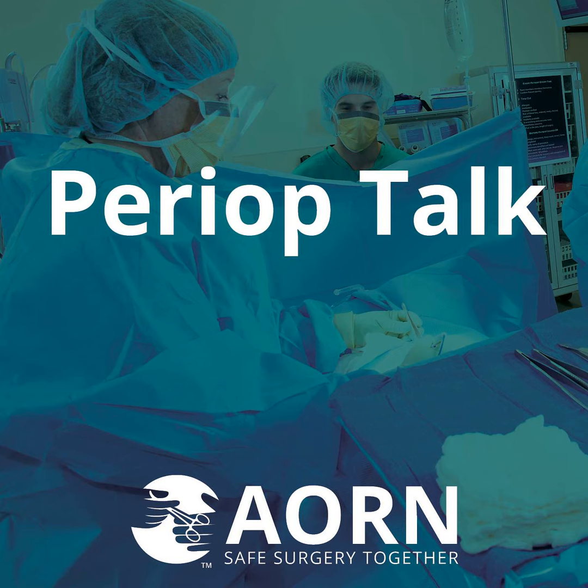Review the IFU of those pouches and the items that you're putting into pouches, and coach your team. Give just-in-time coaching, looking at the seal quality and the type of items being packaged. And it's important for leaders to listen to the frontline team. The people who are doing the work know how to improve the process. So listen to them. Maybe you need different sizes of pouches. Maybe some of the items need to be moved to a rigid container or a wrapped tray. Those things are going to take resources.